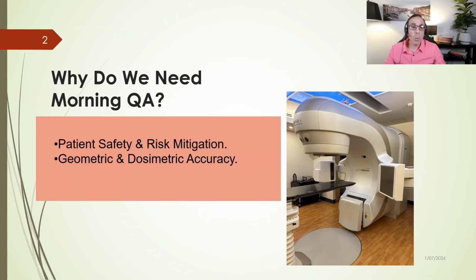Usually these changes are very small. You cannot see them during normal use, however, modern radiotherapy requires millimeter accuracy. A mistake of just a few percent in the dose can affect patient safety. Therefore, small changes are actually a big problem. This is why morning QA is our first line of defense.